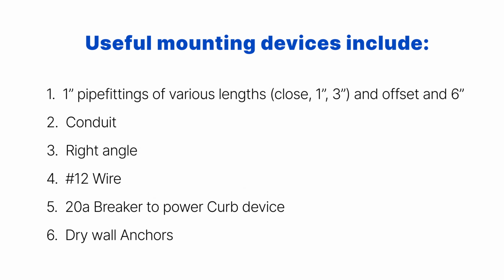In addition to the Curb device components, there's a handful of useful mounting devices. We recommend including 1-inch pipe fittings of various lengths, a close, a 1-inch, a 3-inch, an offset, and even a 6-inch. We also recommend having conduit, a right angle, number 12 wire, and a 20 amp breaker to power the Curb device. Also, think about how you're going to be mounting the Curb box and the right type of drywall anchors or brick anchors that you would use for installing the Curb device.